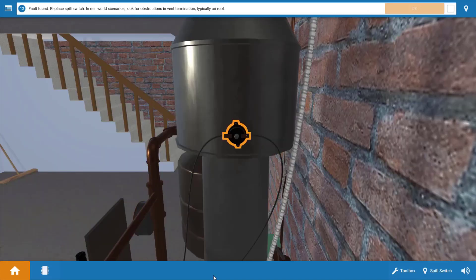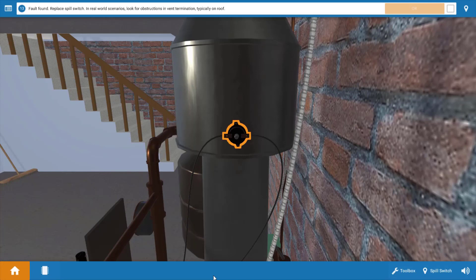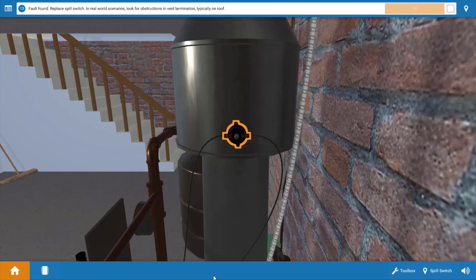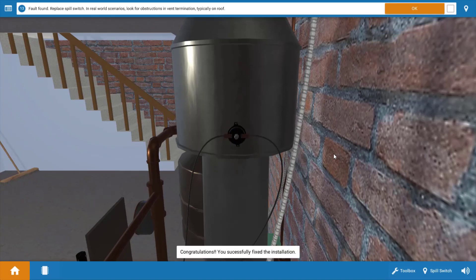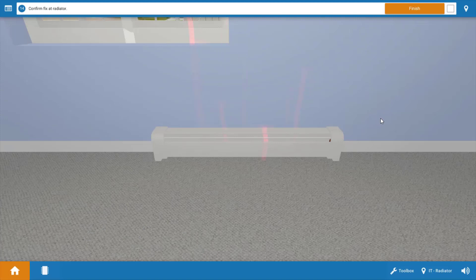Now it's going to be very important to not just simply replace the spill switch. In most cases the spill switch is opening due to some condition. This could be something like an obstruction in the vent, poor vent design, or possibly a competing exhaust appliance nearby that's pulling combustion gases out of the draft hood causing the spill switch to open. After you've found and corrected these issues simply click on the spill switch and replace it.